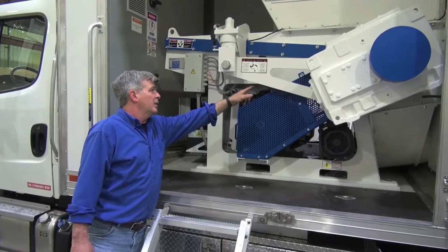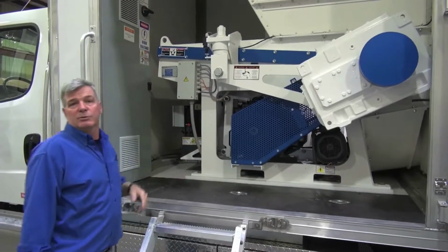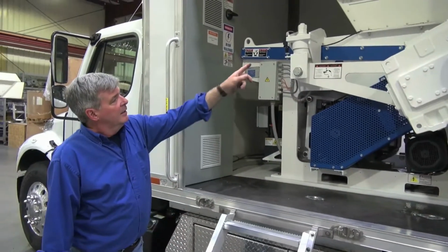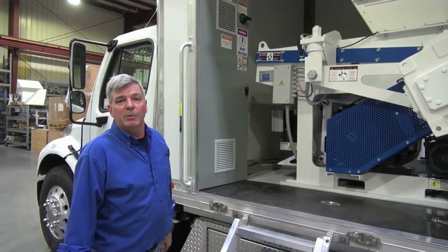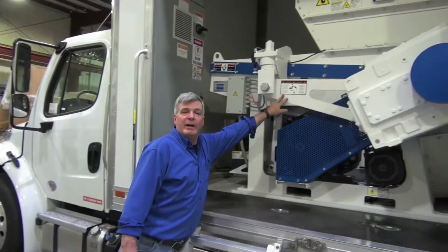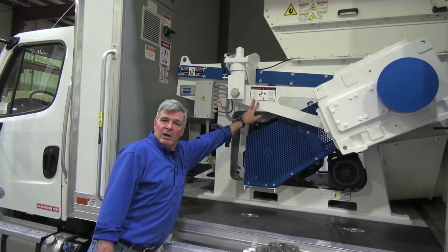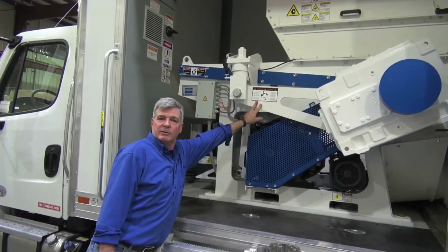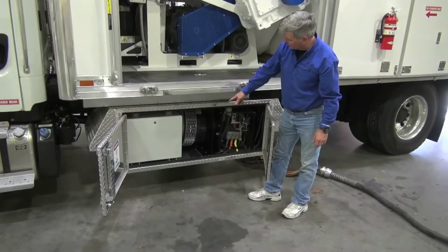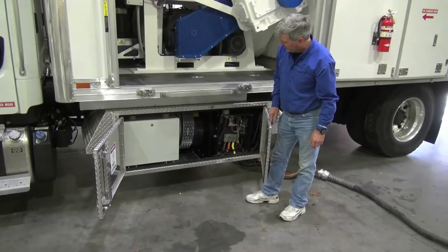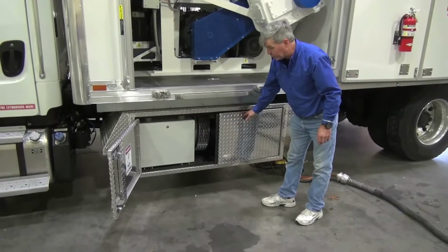could be hurt. There's placards on all of these things to let you know that. Rotor, if ever you're doing any welding on the rotor, it's important that your ground is attached to the rotor. Otherwise you can damage the bearings. The generator is housed within the toolbox. There is high voltage within this.